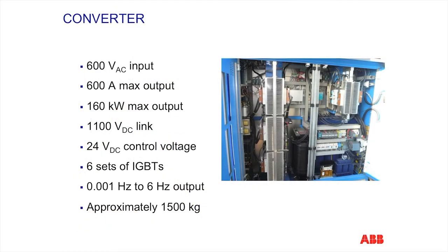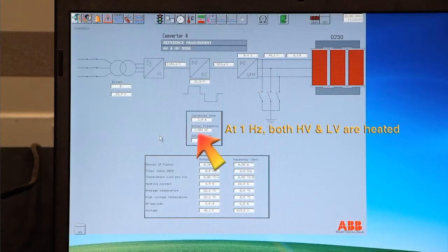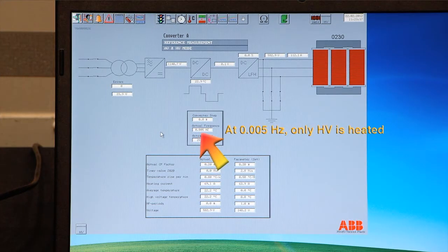The windings are heated through the interaction of 2 parameters. One is the current factor, or CF value, and the other is the frequency. The LFH plant can vary the frequency from 6 Hz down to 0.001 Hz. The latter is commonly stated in millihertz, with the lowest value being 1 millihertz. At the high end of the frequency range, heating of the low-voltage windings takes place because of the AC inductive effect. At the low-frequency end, only the high-voltage winding is heated, as the system approaches the behavior of a DC heated winding. The frequency cycles between step points designed to heat only the high-voltage winding and then both windings.